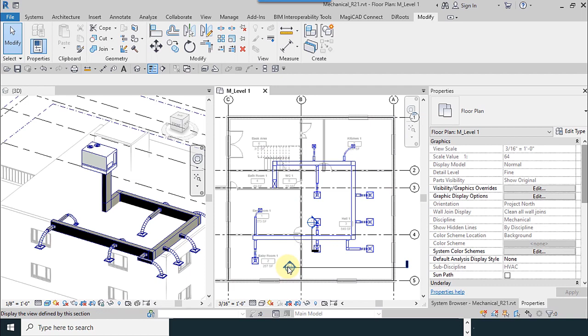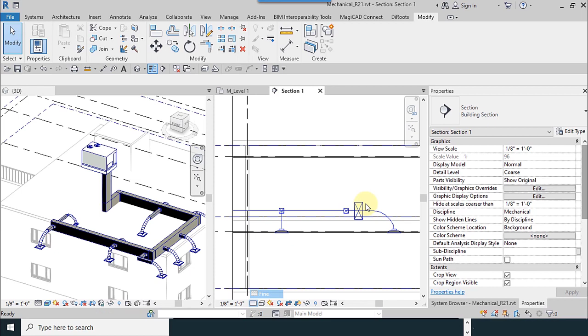So now we go to the calculations. Important note: I just saw the height of the drop ceiling. We have to rectify some of them which are out of the ceiling. I checked the size, approximately 1 foot. We have to change the installation of the ducts. For example, our support is near 10 centimeters and 2 or 3 centimeters for the insulation.